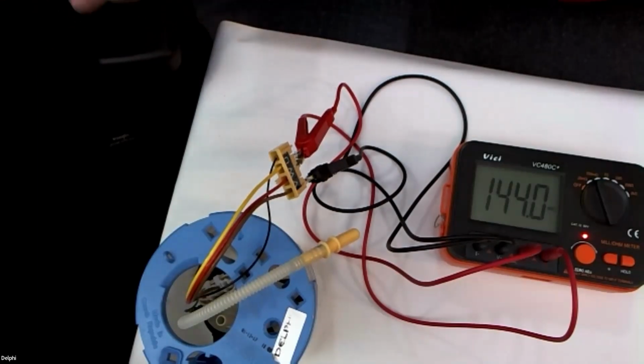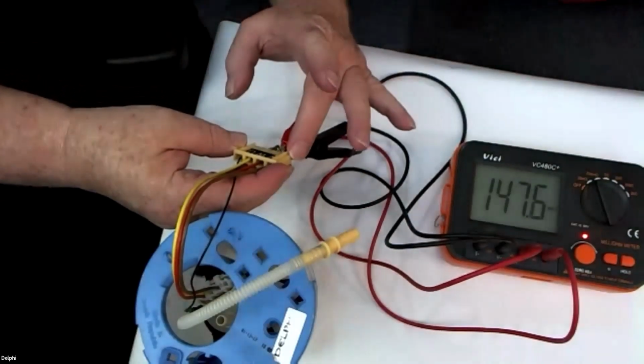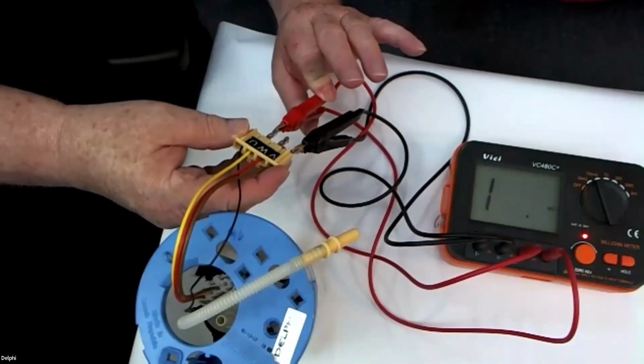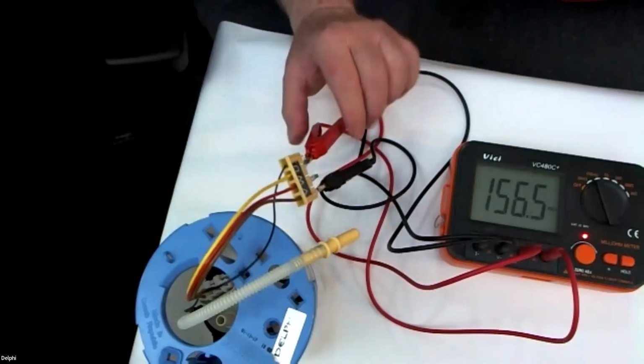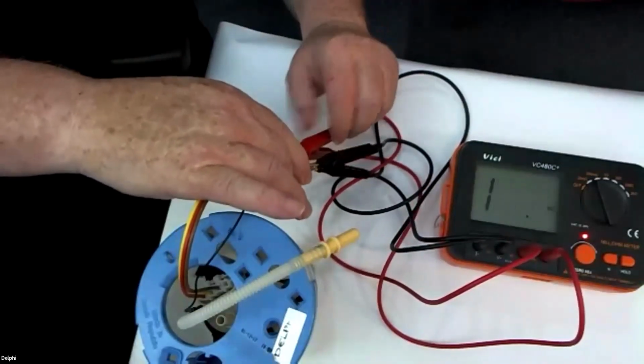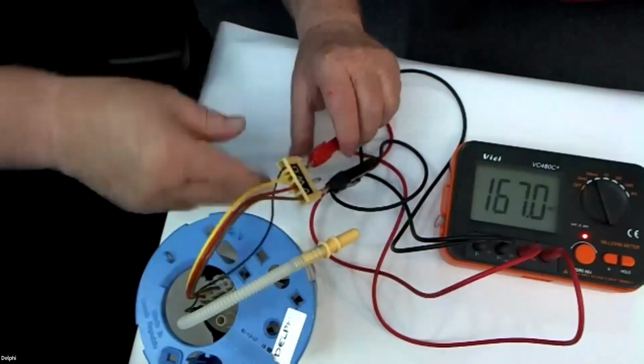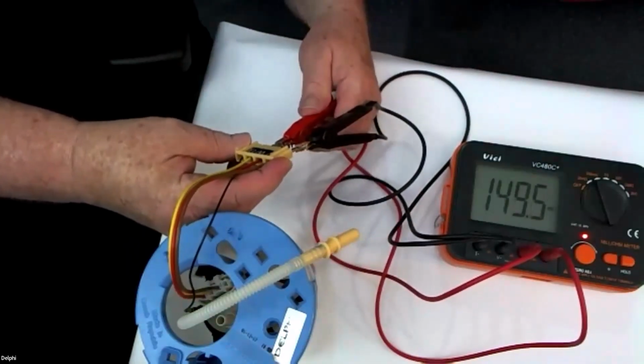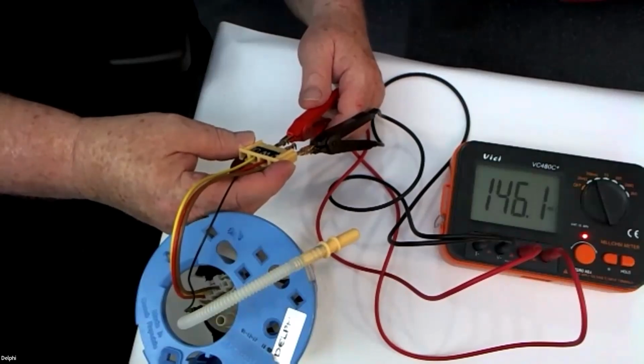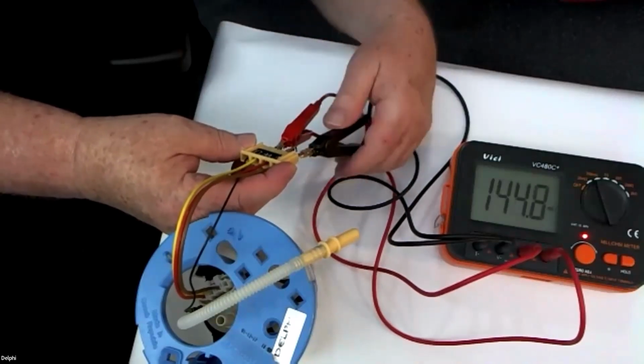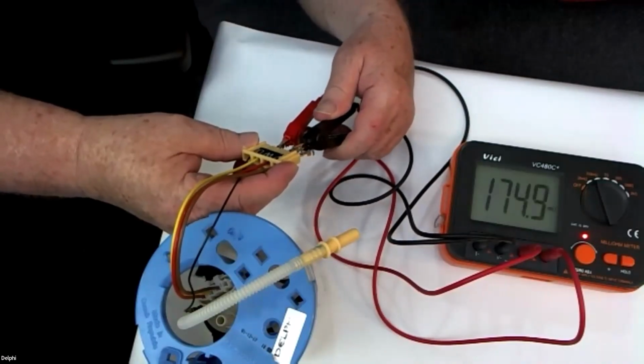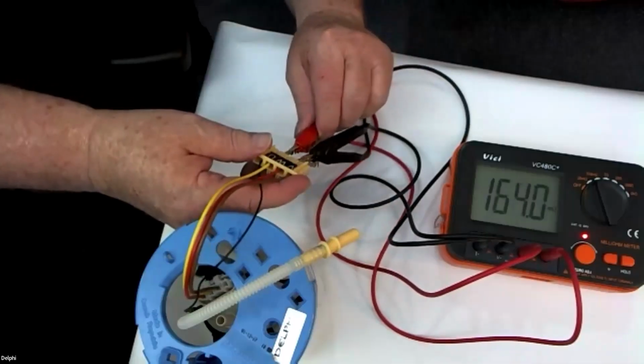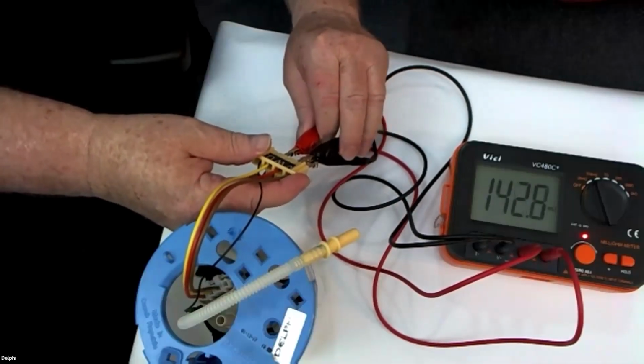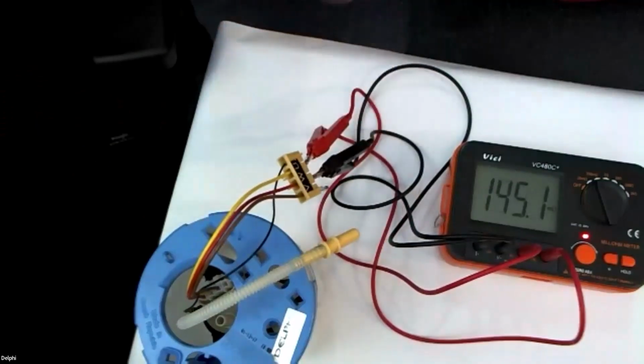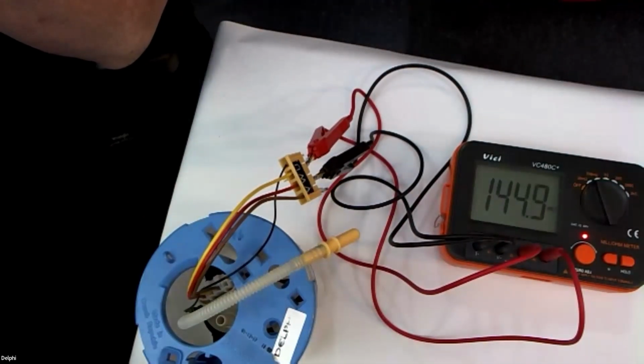But that's just one combination of the 3 phases - that's Victor to whiskey, V to W. Let's go V to U, doing the same thing. What do we have here? Make sure we're getting good connections. We're doing something wrong here, either that or I've broken this. There we go, if I can hold it still - 145, 146. Now let's go whiskey, W to U, so all the combinations. There we go again, a little bit of fluctuation, get a good bite, and we're seeing like 142. So 142 to 144 - you saw the specs published from the Toyota service manual, and that's what you're looking for.